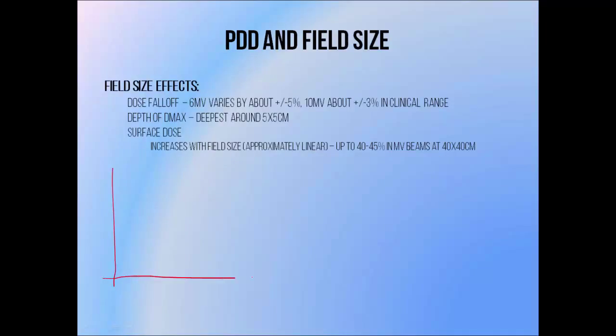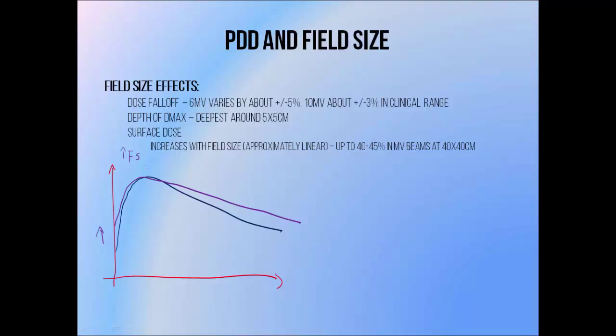PDD shape depends on radiation field size — that is, the size of the beam and the amount of material inside the beam. When we increase the field size we see three major effects. First, the surface dose increases. An MV beam with a 10x10 cm field will normally have a surface dose of 10–15%. When we increase to the maximum of 40x40 cm, it rises to about 40–45%, and tends to be highest in large field sizes with high beam energies. Second, the depth of maximum dose tends to move slightly towards the surface, being deepest at around 5x5 cm and becoming shallower if we increase or decrease the field size.